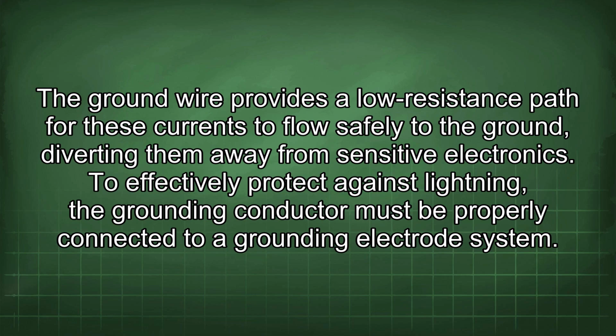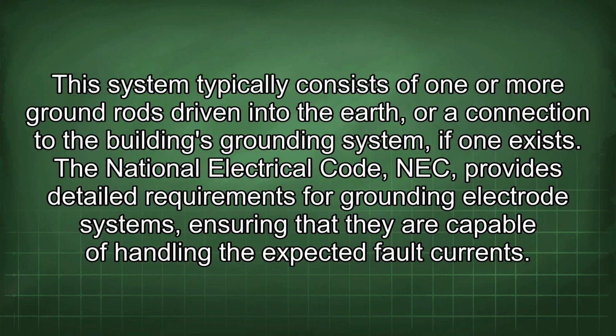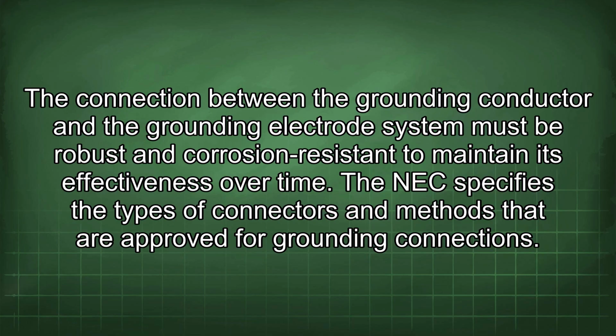The ground wire provides a low-resistance path for these currents to flow safely to the ground, diverting them away from sensitive electronics. To effectively protect against lightning, the grounding conductor must be properly connected to a grounding electrode system. This system typically consists of one or more ground rods driven into the earth, or a connection to the building's grounding system if one exists. The National Electrical Code, NEC, provides detailed requirements for grounding electrode systems, ensuring that they are capable of handling the expected fault currents. The connection between the grounding conductor and the grounding electrode system must be robust and corrosion-resistant to maintain its effectiveness over time. The NEC specifies the types of connectors and methods that are approved for grounding connections.